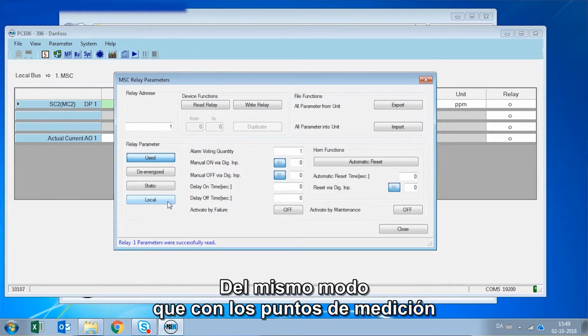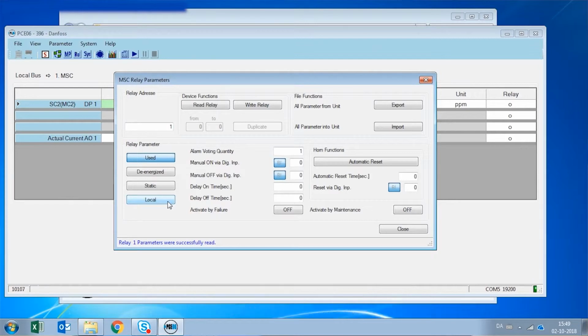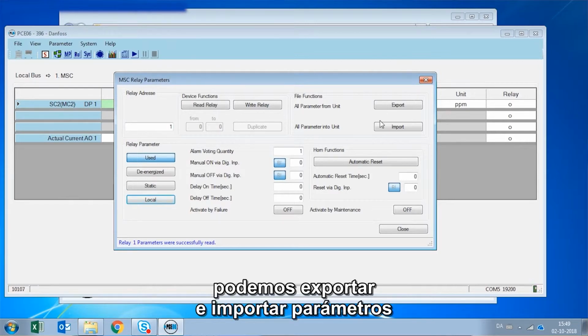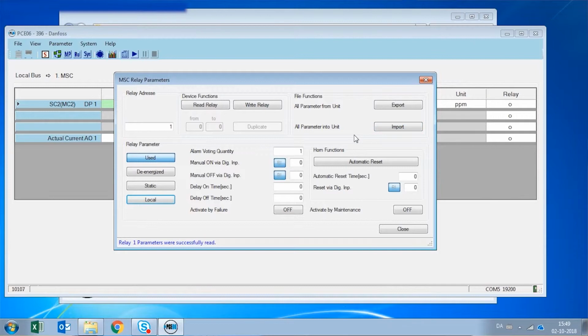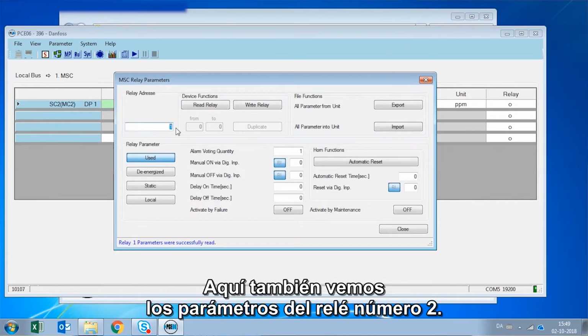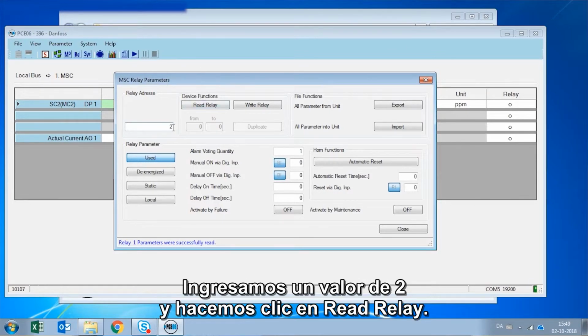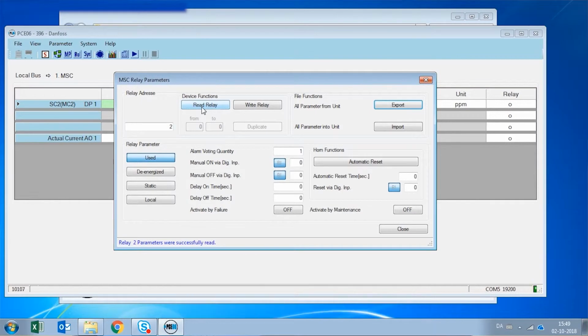The same way that we have seen with the measuring point, we can export and import parameters from other relays. And here you can see also the parameters of relay number 2. We enter value number 2 and we set read relay.